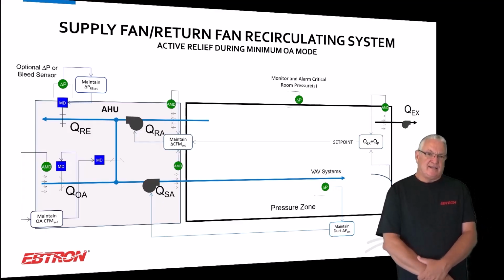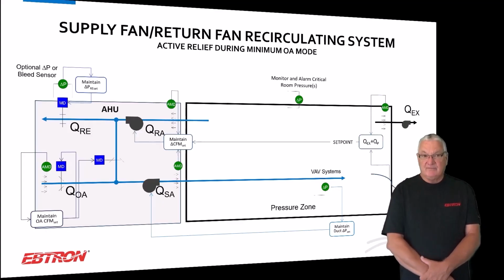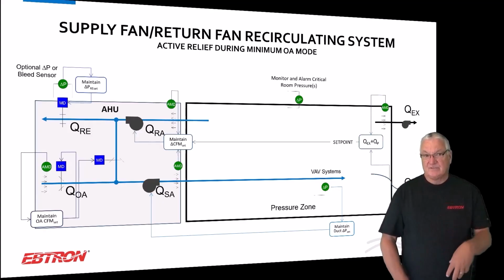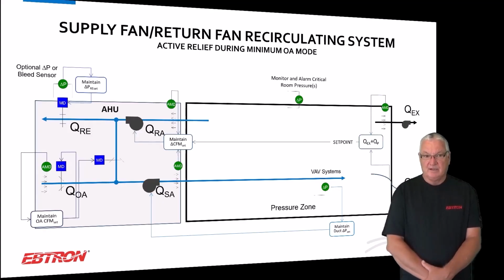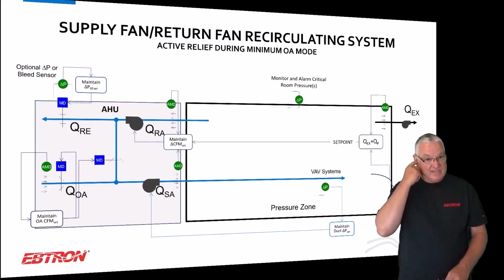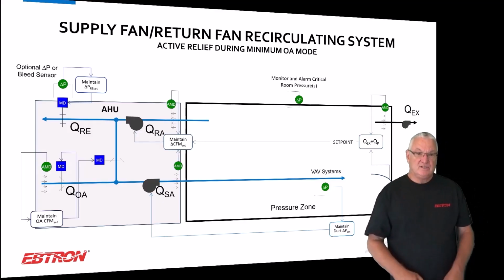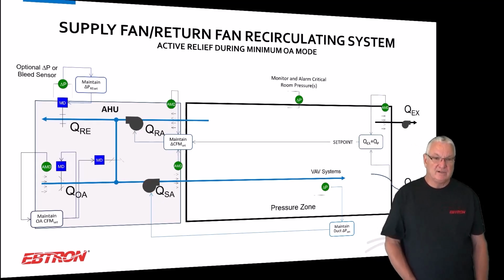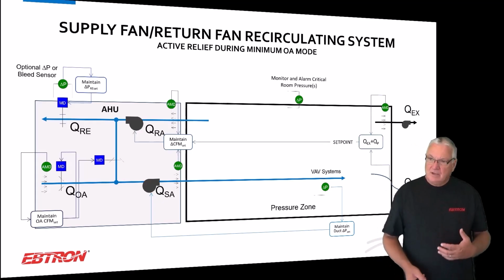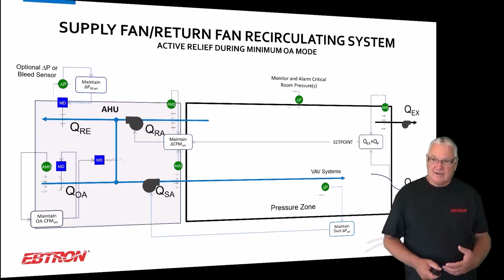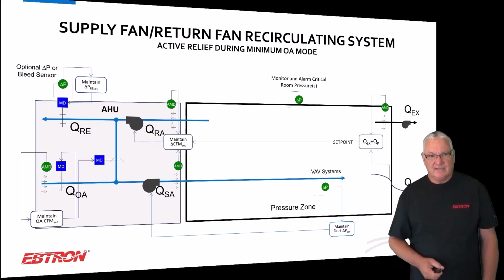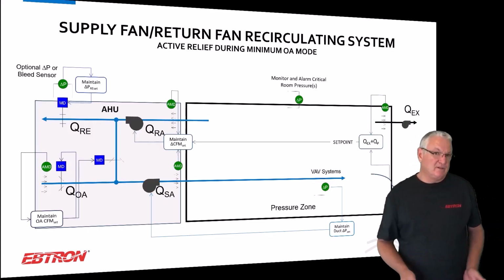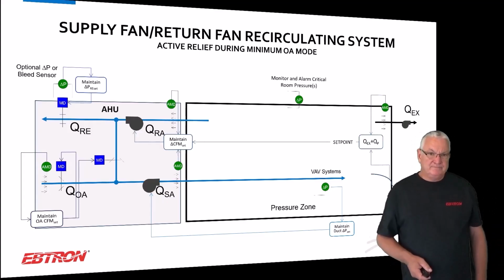And the reason for that is that when you're not relieving air, using that return air fan strategy that we had just previously talked about, your mixed air is negative, obviously, to the outside of the building, but your discharge of the return fan could be too, okay. And so you don't want to go from this mode where you crack that outside air damper and that relief air damper, and then you're bringing in outside air through the relief, because you don't know where that relief path is located, or it may not be located where you want it to be.